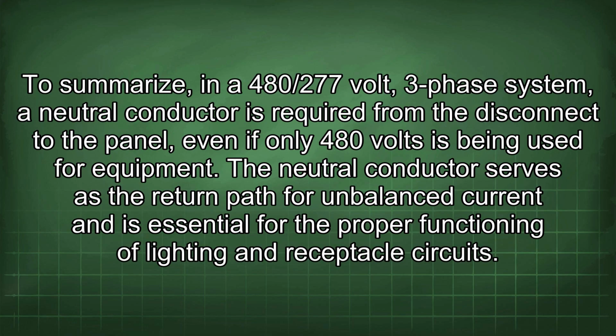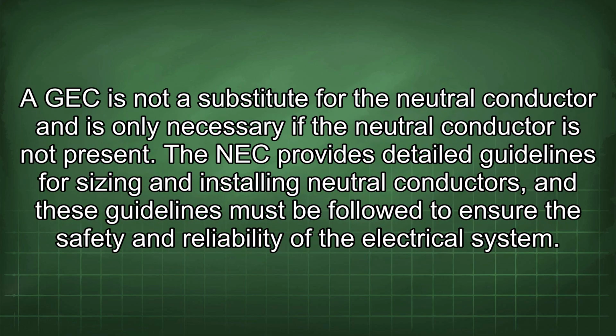To summarize, in a 480/277 volt three-phase system, a neutral conductor is required from the disconnect to the panel, even if only 480 volts is being used for equipment. The neutral conductor serves as the return path for unbalanced current and is essential for the proper functioning of lighting and receptacle circuits. A GEC is not a substitute for the neutral conductor and is only necessary if the neutral conductor is not present. The NEC provides detailed guidelines for sizing and installing neutral conductors, and these guidelines must be followed to ensure the safety and reliability of the electrical system.